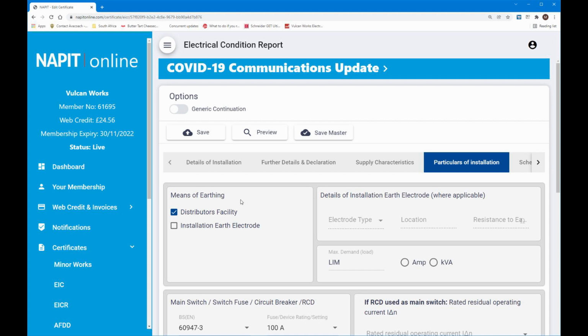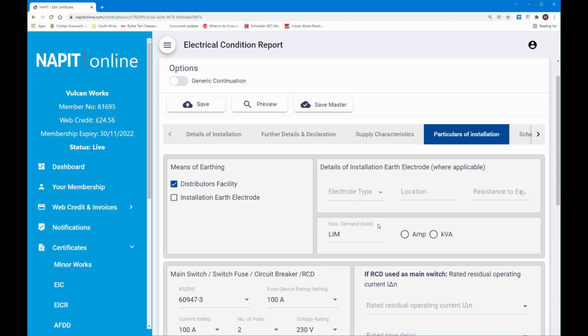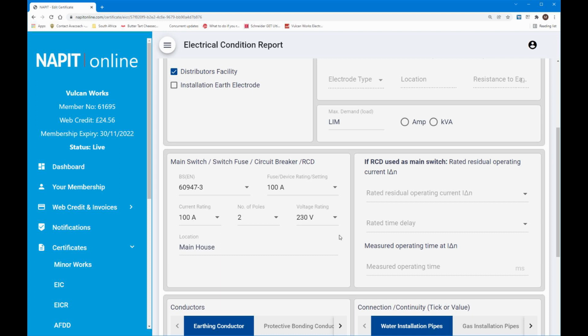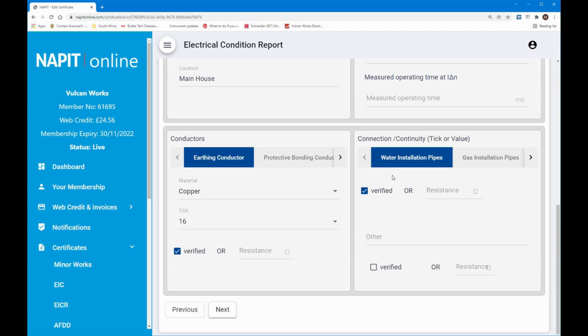So, the means of earthing for this property is at the distributor's facility. It's not a TT system. I didn't do the maximum demand, so that's a limitation. The main switch in the main consumer unit is a BS EN 60947-3 at 100 amps, 100 amp current rated, number of poles 2. Voltage rating 230 volts, and it's in the main house. It's not an RCD.